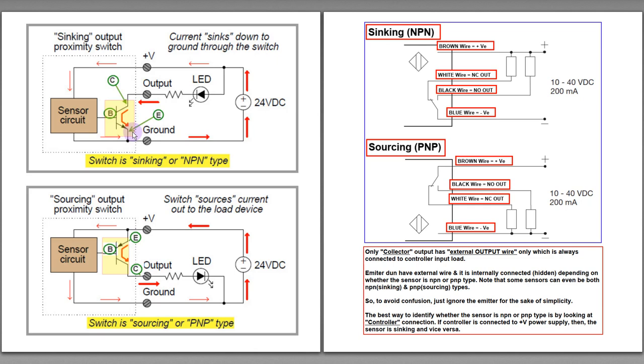As for the E emitter, it can be either internally connected to the negative V or the ground wiring, or it can be internally connected to the positive V. This depends on whether it is a sinking or a sourcing type. If this switch is a sinking or NPN type switch, then the E emitter will be connected to the ground or negative V wiring. If the switch is a sourcing or PNP type switch, then the E emitter is internally connected to the positive V wiring.